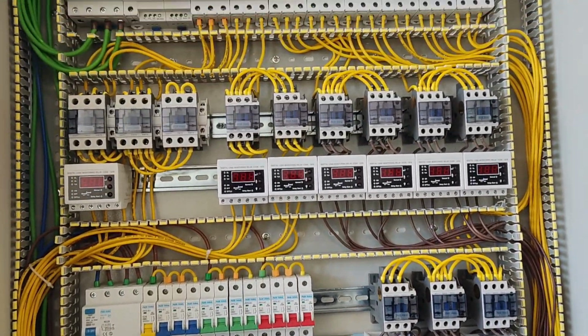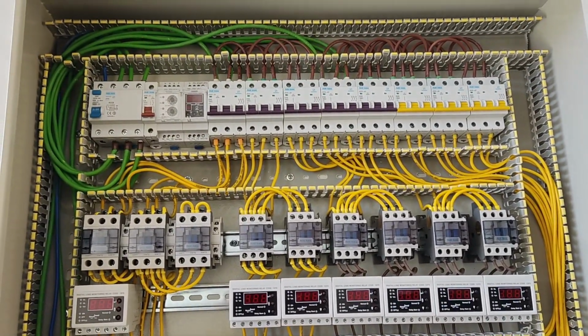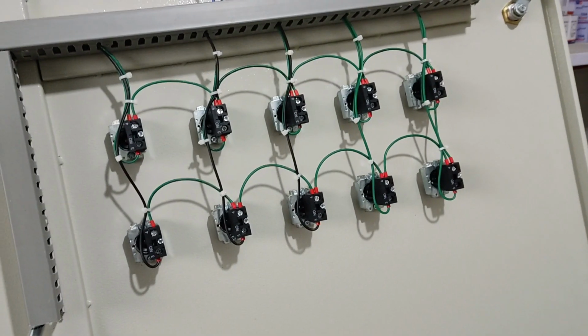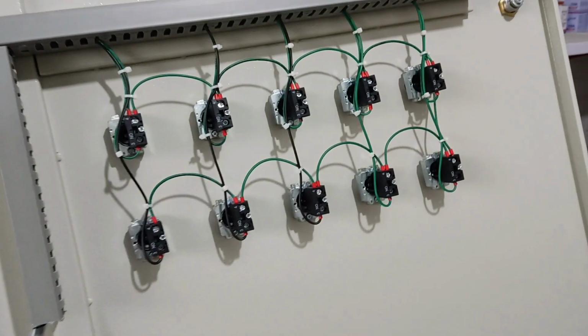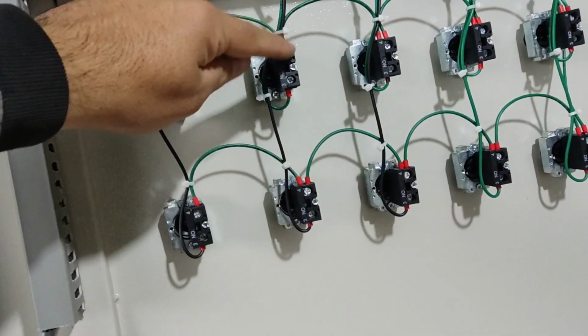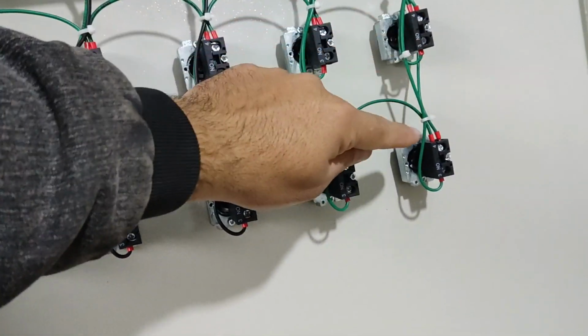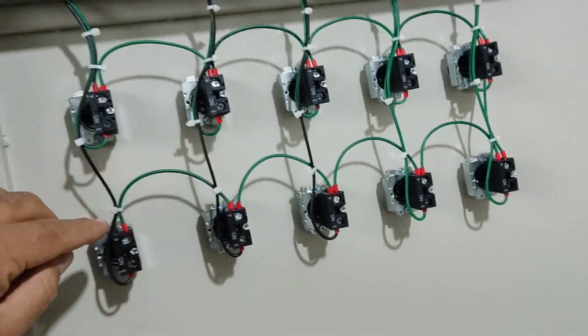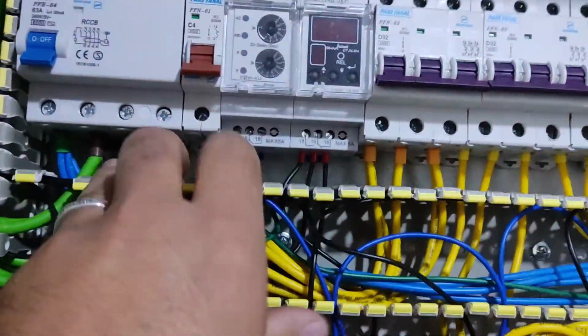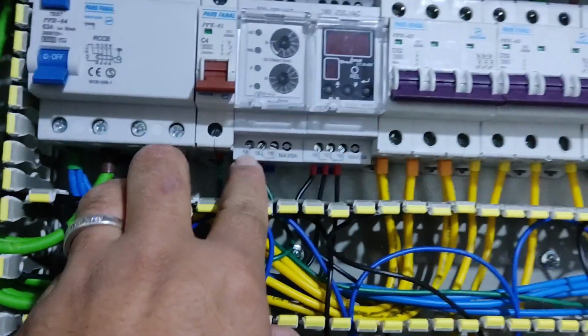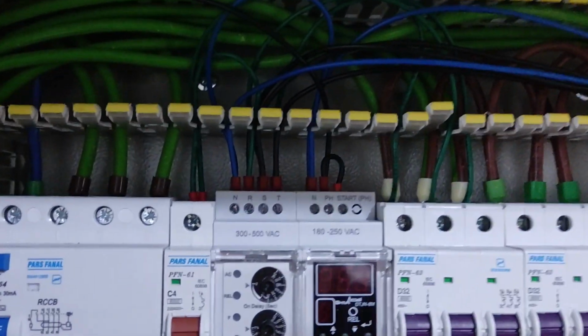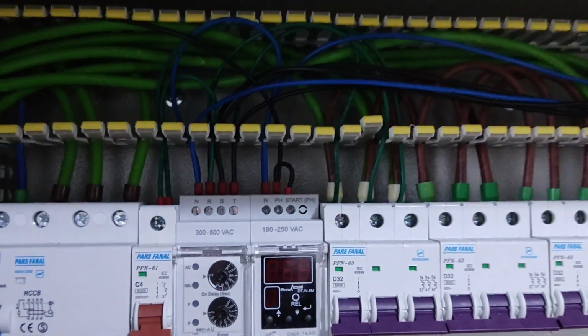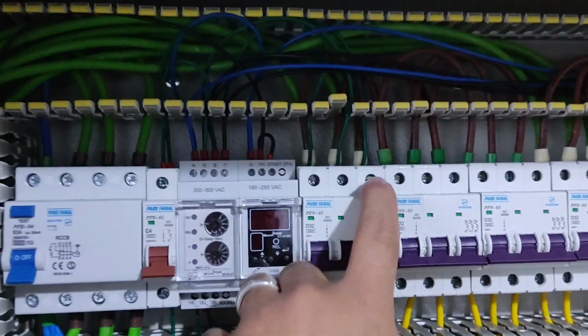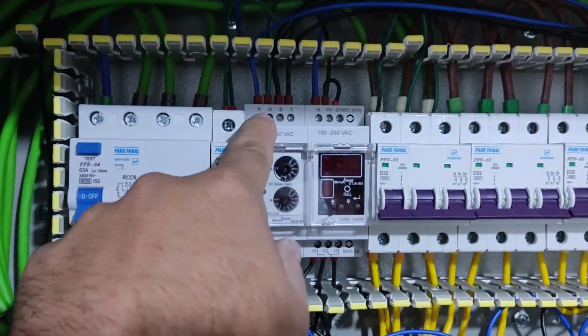Now we are wiring the control circuit. In this electrical panel, we have installed 10 selector switches on the door of the electrical panel to turn on and turn off the three-phase contactor. The input of all these switches is connected to the output of the phase controller relay, which is pin 18. And as you can see, the relay inputs are connected to three phases to measure their voltage.